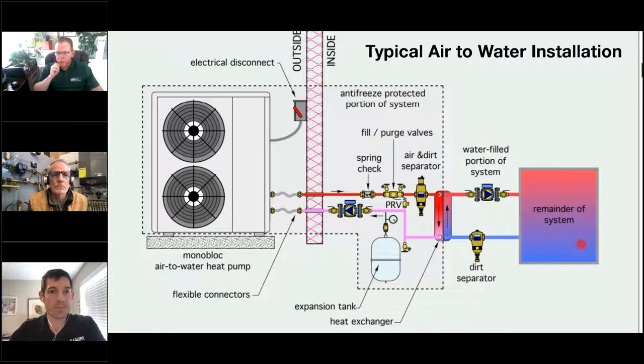Sort of touching on some of the things for Bob, because I have installed a few of these. So key things to keep in mind is that this unit outside, we're showing it here just sitting on a pad. Be aware that depending on your climate, this isn't a good idea. So if you go back to the photo of mine, this is just a general photo that Caleffi is using. We need to be above the snow level. So you need to make sure it's on a snow stand. In my case, I actually mounted it off the wall with just a giant stand. Typically, you want about 18 inches of clearance for your snow stand. Those of you in, I know Lee is on this call, and she's in Northern Ontario, even 18 inches, she's still going to have snow issues, but we want to make sure it's up.